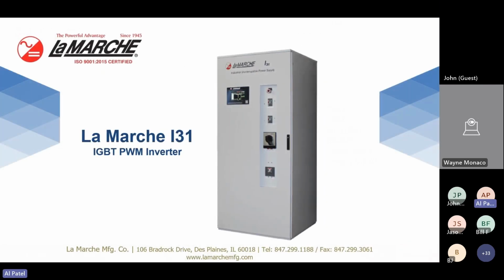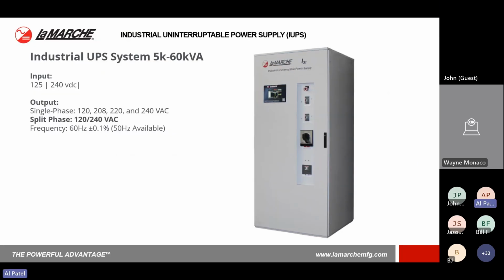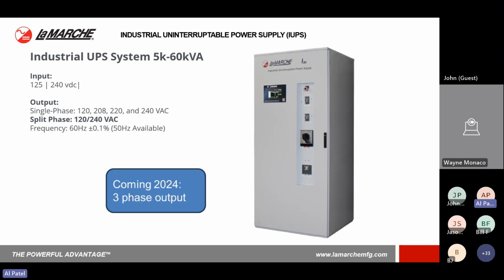We have also decided to offer an industrial grade inverter system, which goes beyond our other products that we offer. That's part of our product portfolio, our A31. The A31 design, the control ferro design, was limited to about 15 kVA. However, our I31 will go up to 60 kVA. It does come in a 125 and 240 VDC offering, and we also provide single phase output along with split phase. And again, we will have a 3-phase output available in 2024.